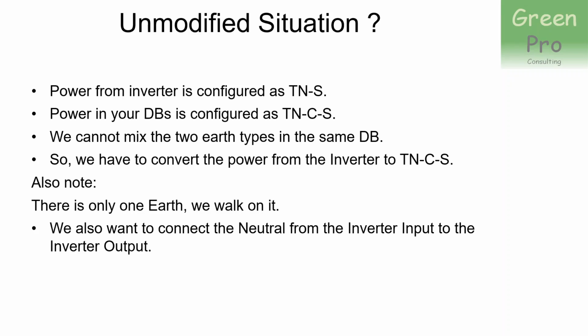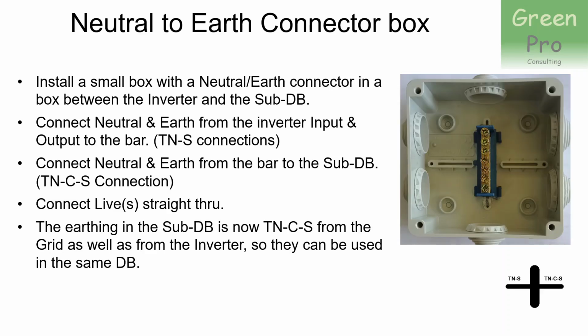I also like to connect the neutral from the inverter input to the inverter output. I find if you don't do that and you have a long supply line from your point of supply to your main DB, then you just get that slight deviation in the neutral voltage, like 0.1 volt or something. But that's often enough to make an earth leakage trip, and then you have nuisance tripping. So I prefer to use a neutral before the inverter and after the inverter, and connect them to each other.